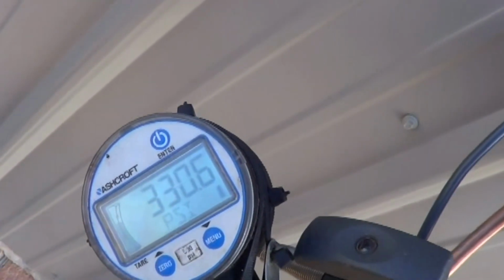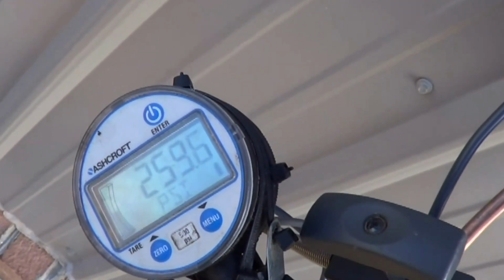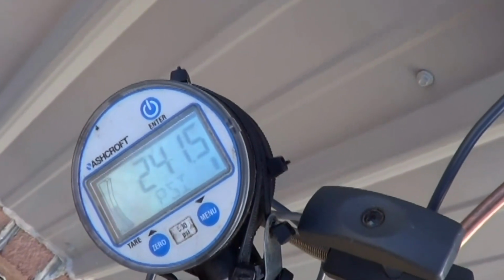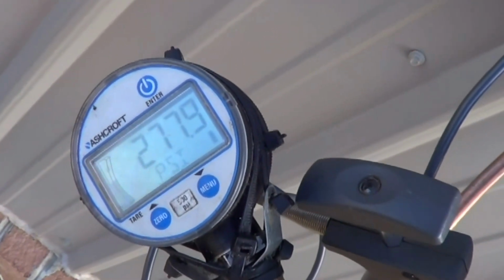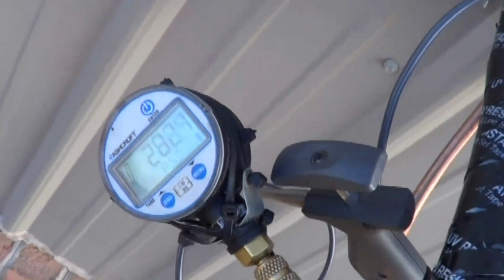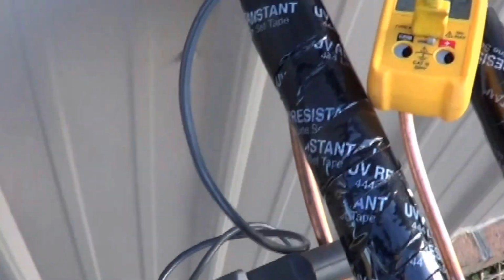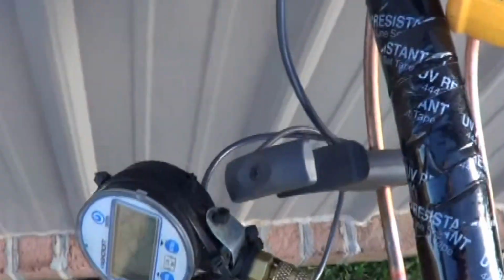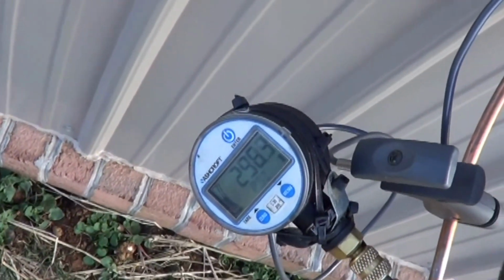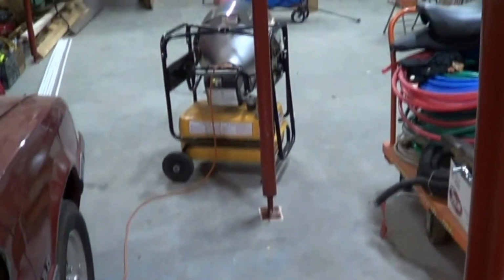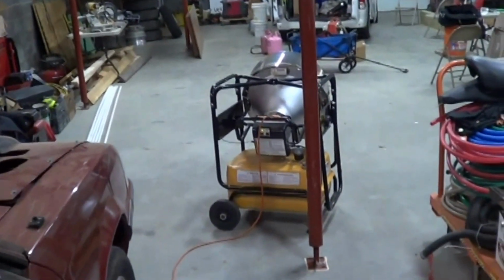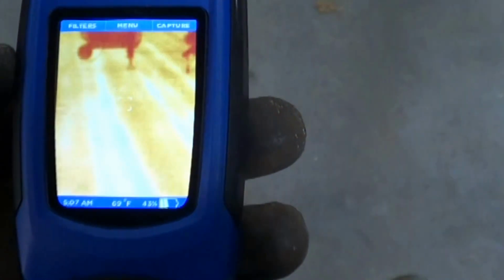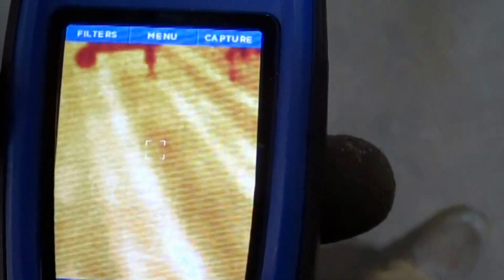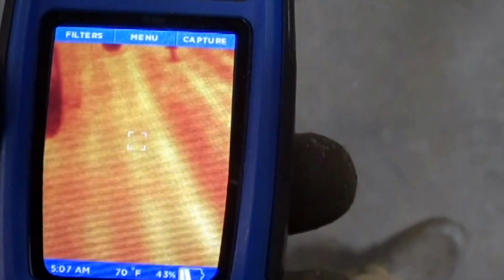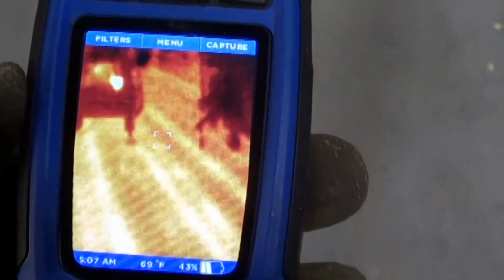You can see I'll bring down my head, because that's the standby circuit, not going to be used until summer. And we'll go back and check our subcooling, and also the thermal camera would show this. So the room's about 67 degrees, and the floor, you can see here, 70 degrees, 71. You can see the pipes in the floor.